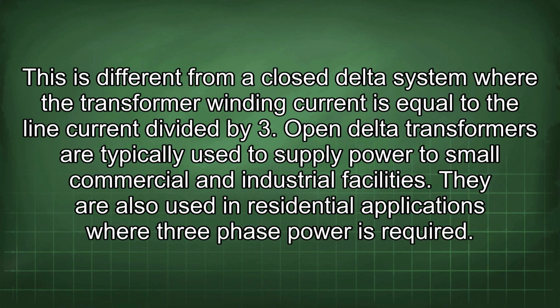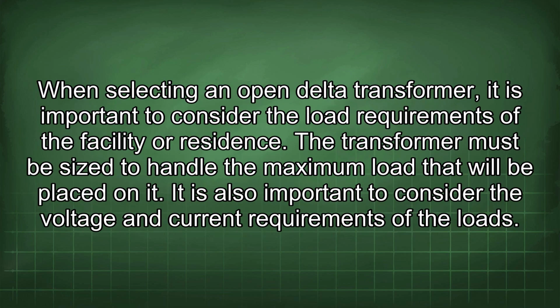This is different from a closed delta system where the transformer winding current is equal to the line current divided by 3. Open delta transformers are typically used to supply power to small commercial and industrial facilities. They are also used in residential applications where three-phase power is required. When selecting an open delta transformer, it is important to consider the load requirements of the facility or residence.